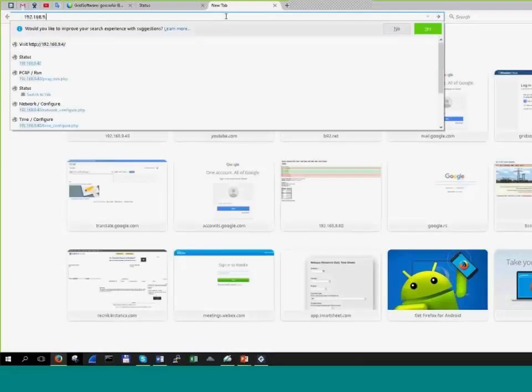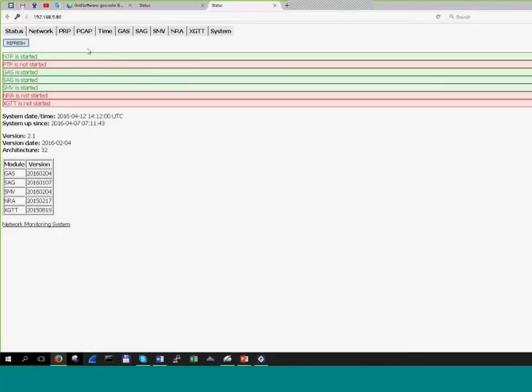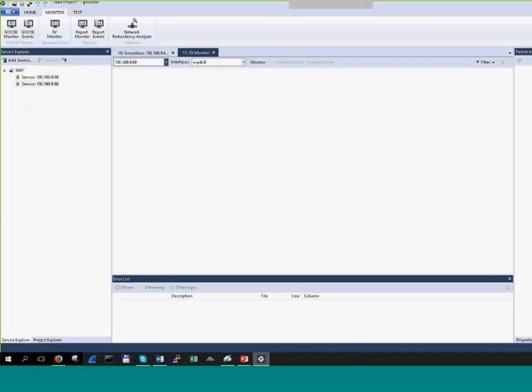Then you can tell the service, hey, you can now go and find any network card on your system and monitor those particular sample values on any of the MAC addresses or network cards that you find on your system. And likewise, when you are publishing a Goose message, all you need to find is the IP address of the Goose publishing service, which is GAS. You tell GAS, I want you to publish this message on one of the interfaces that you see on your system, and you can select which interface. And these IP addresses can be on multiple boxes, and you have the ability to work with multiple gooseAirs.